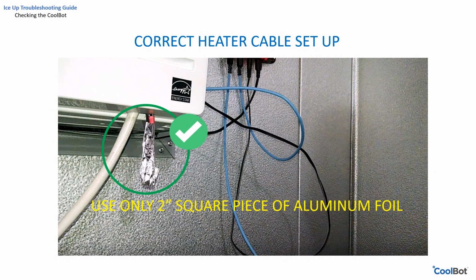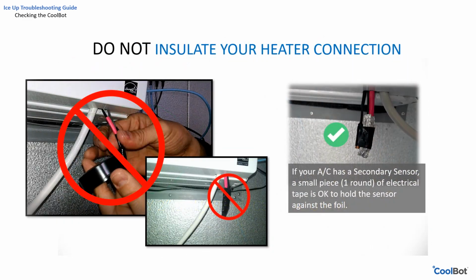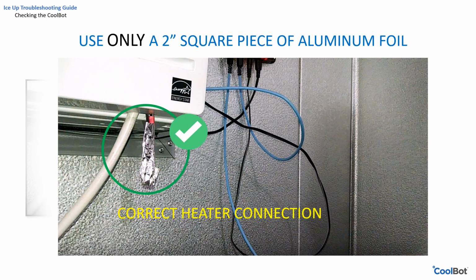The last component to check on the CoolBot is the heater cable installation. Is the heater cable installed correctly? Do not insulate your heater cable and the air conditioner sensor. Use only the piece of aluminum foil recommended in the installation manual. Insulating the heater cable and air conditioner sensor interferes with the intended operation of the heater cable and increases your chances of a freeze-up.